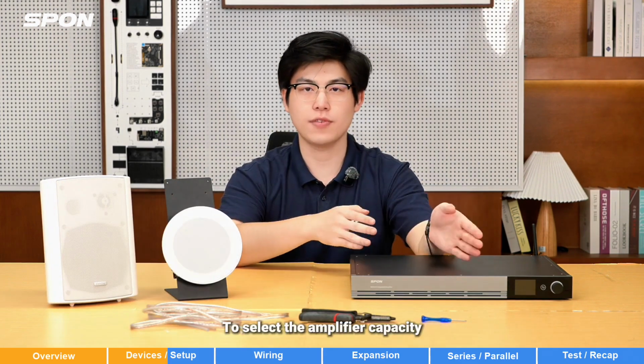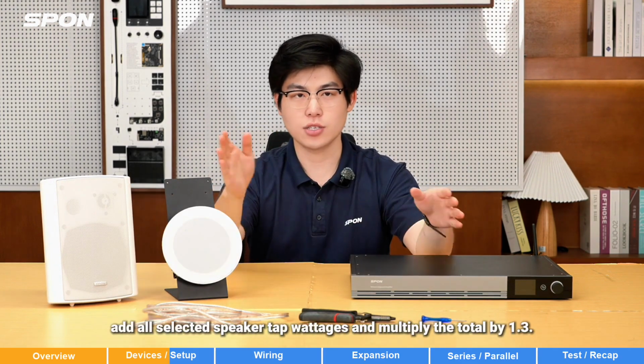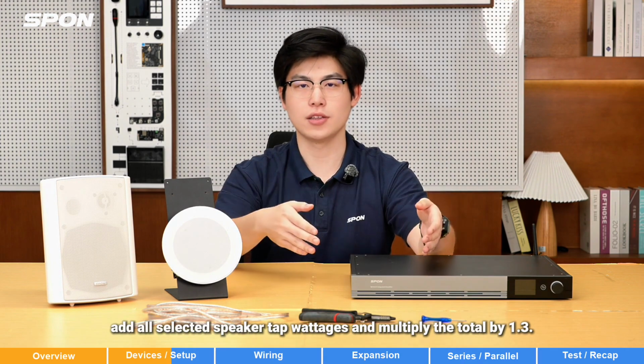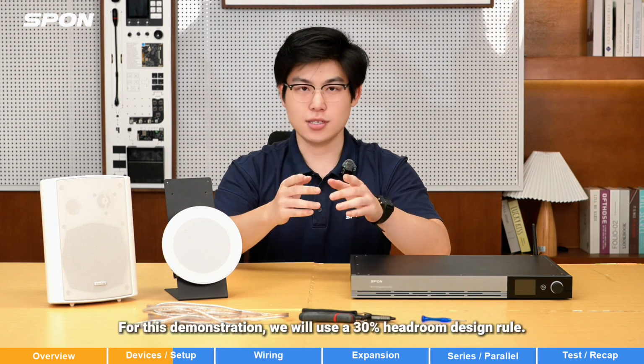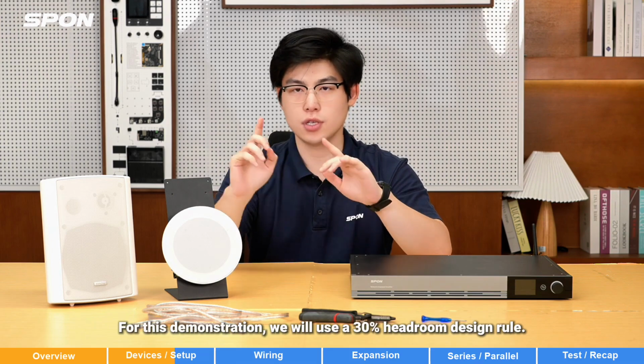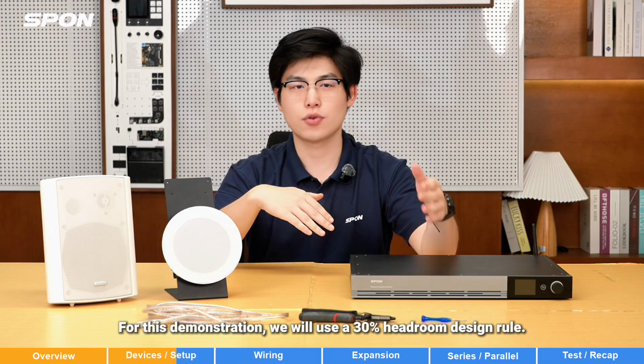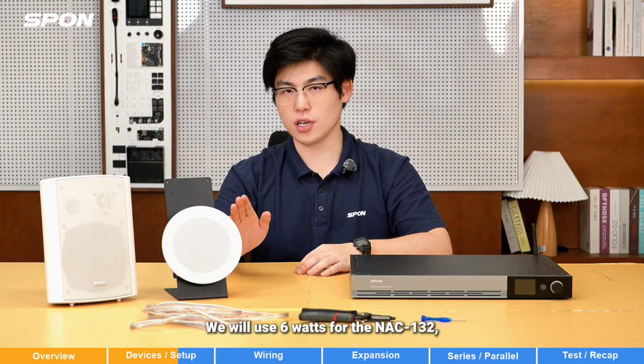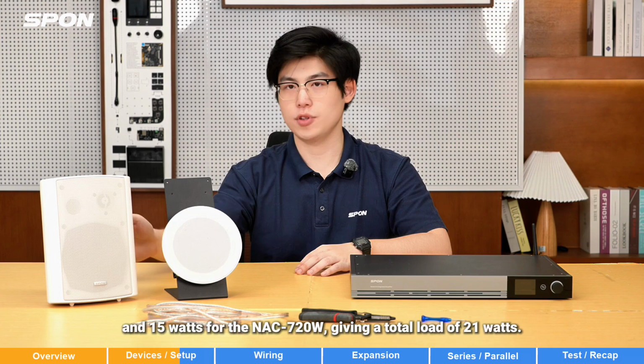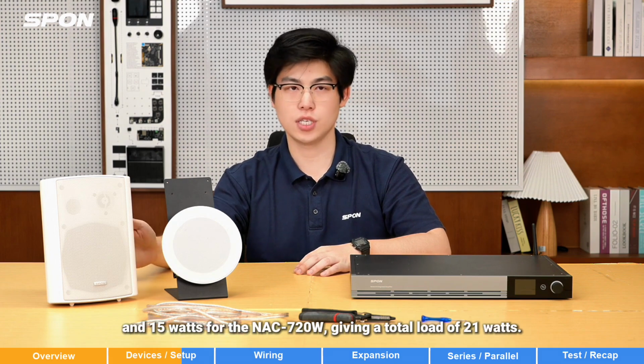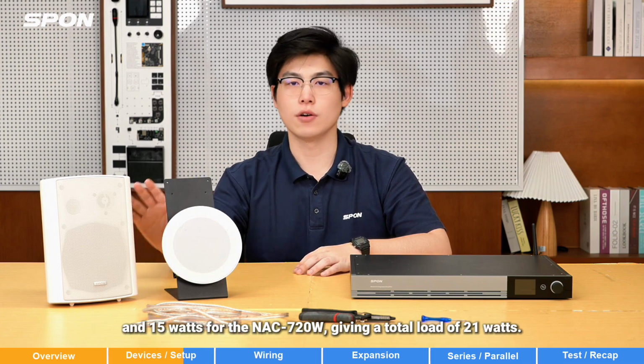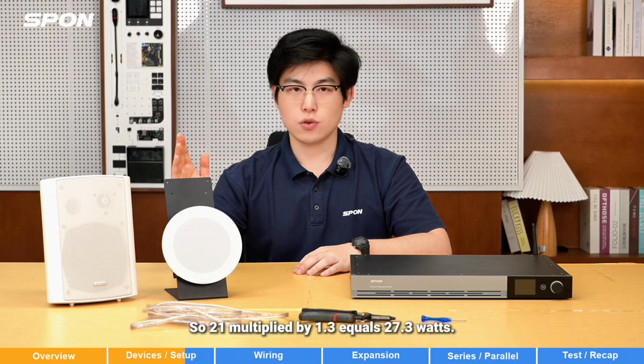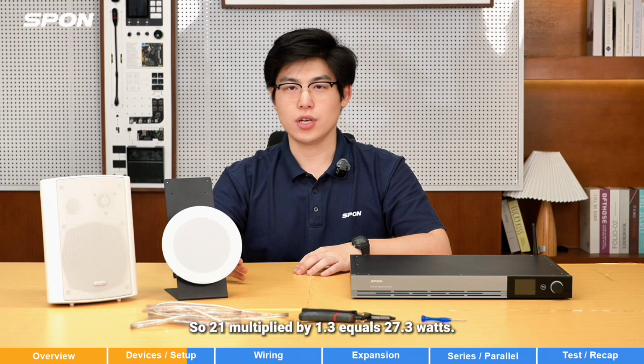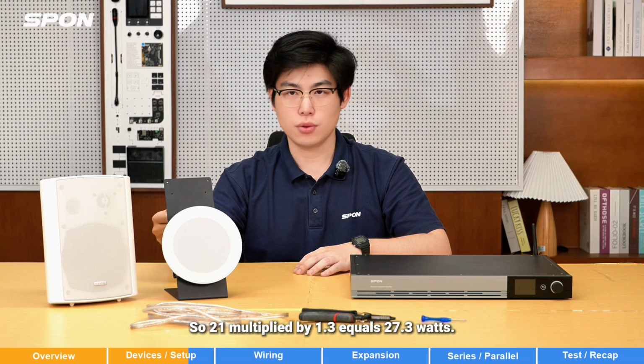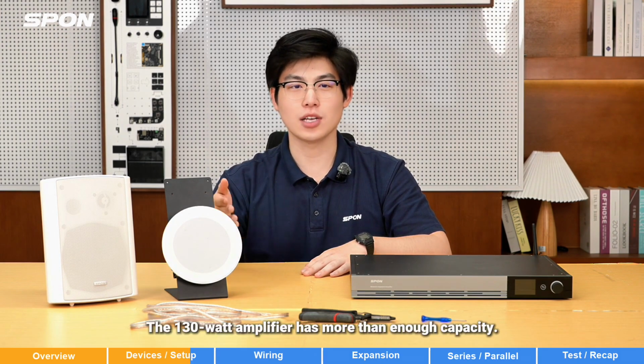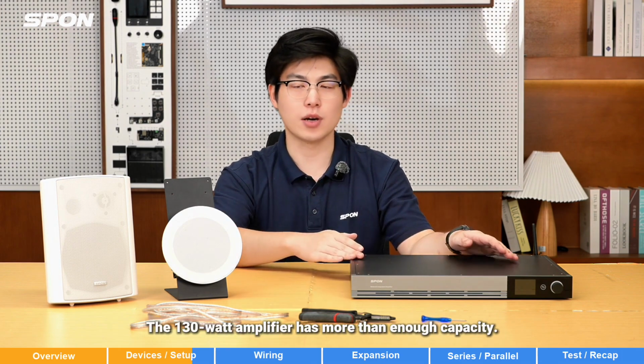To select the amplifier capacity, add all selected speaker tab wattage and multiply the total by 1.3. This is the design rule we will use for the demonstration and also for all your projects. We will use 6 watts for the NAC-132 and 15 watts for the NAC-720W, giving a total load of 21 watts. So 21 multiplied by 1.3 equals 27.3 watts. So the 130 watt amplifier has more than enough capacity.